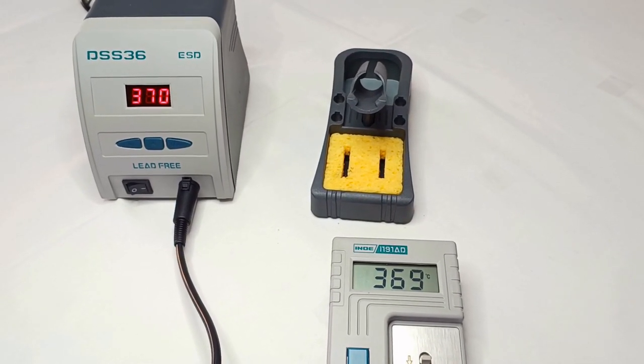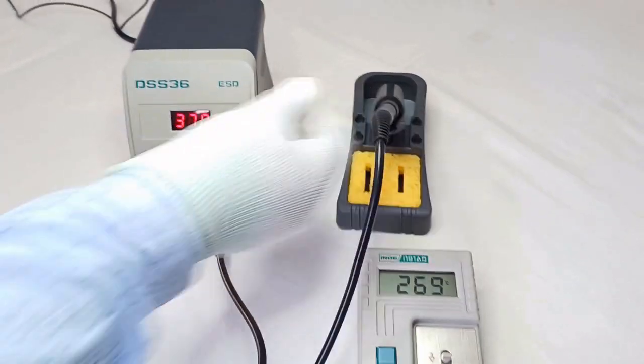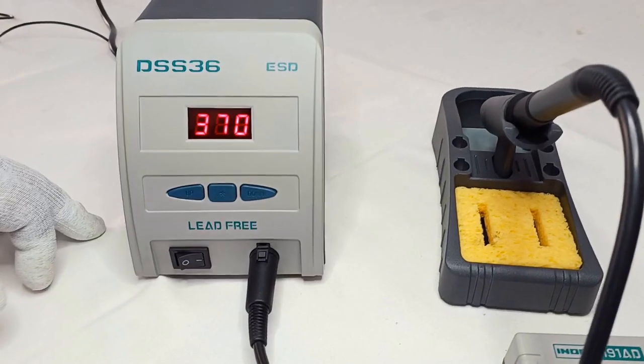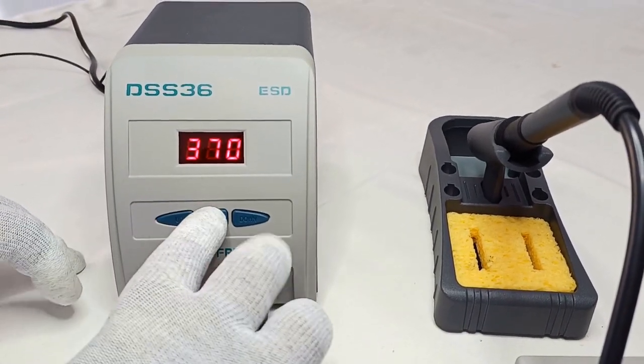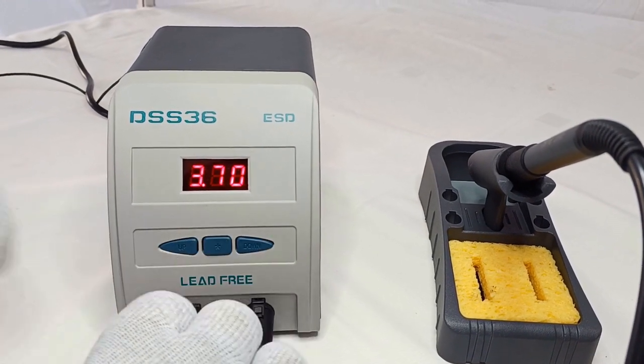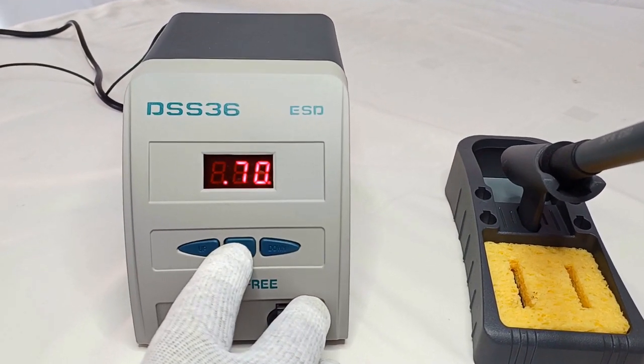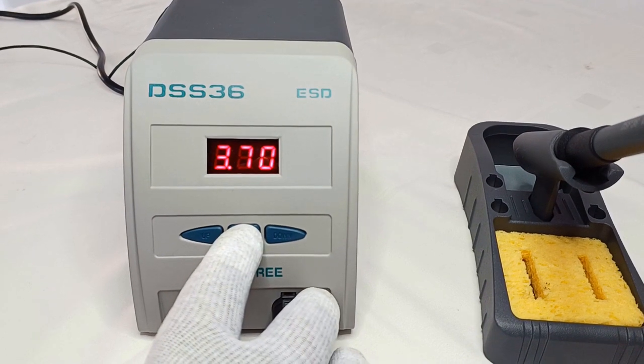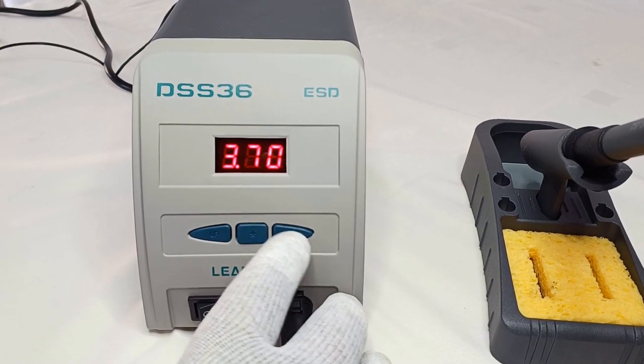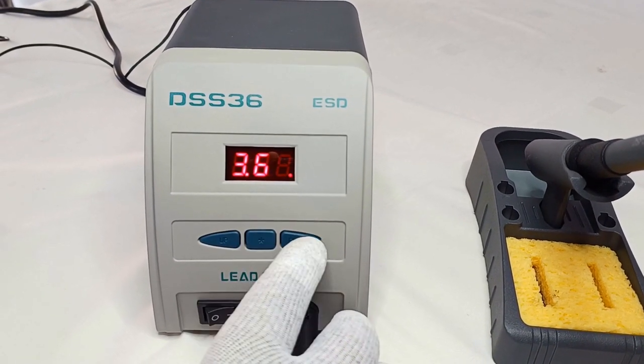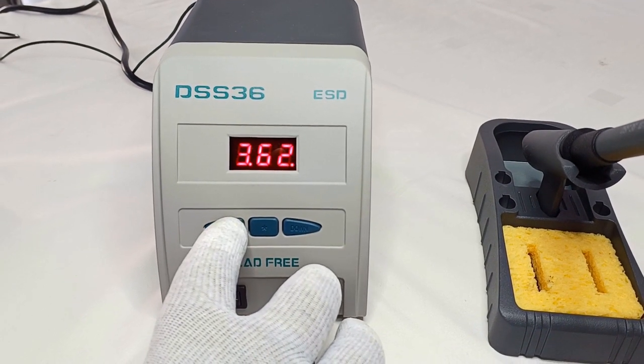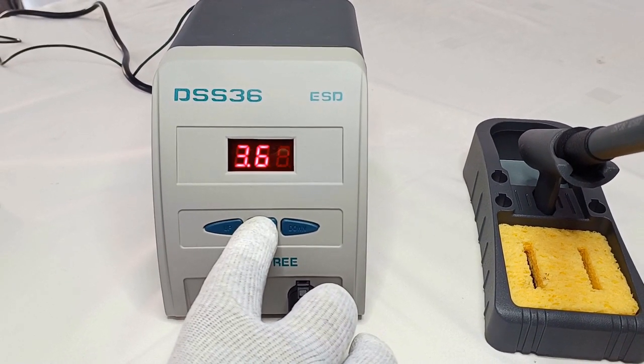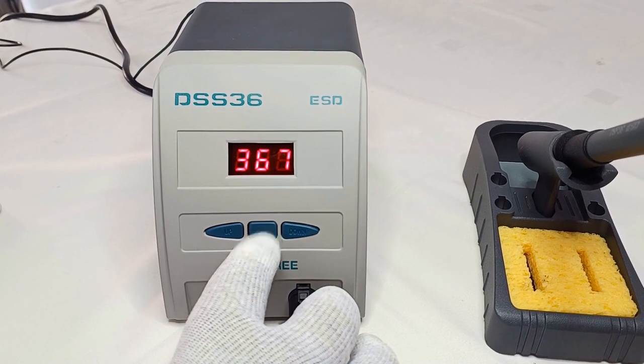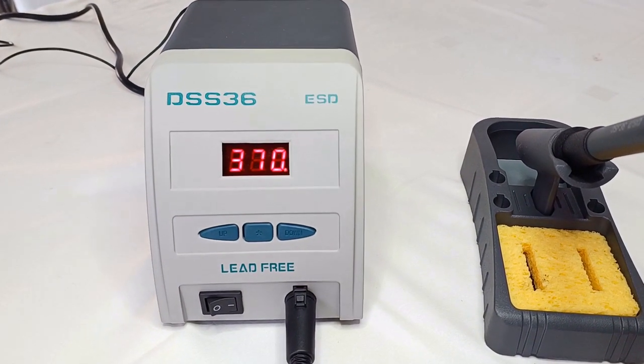So let's use the calibration feature to match the set temperature. First of all, you need to press the star button and then press the up and down buttons simultaneously. Then the digit on the extreme left will start flashing. Then input the same value which you have measured on the external calibrator. Here we will input the value 362 using the up and down buttons and then press the star button. Then you can see the temperature will gradually rise.